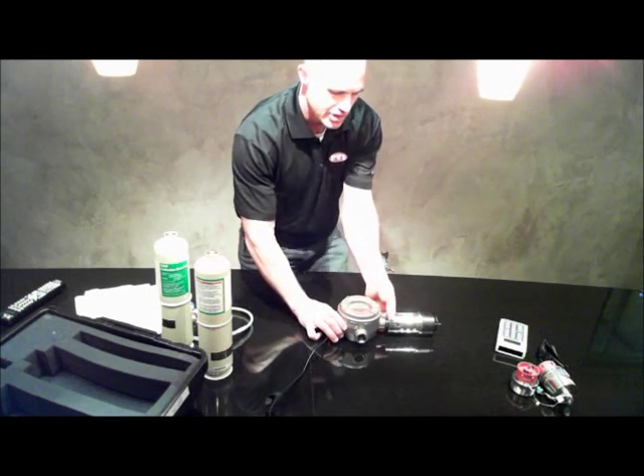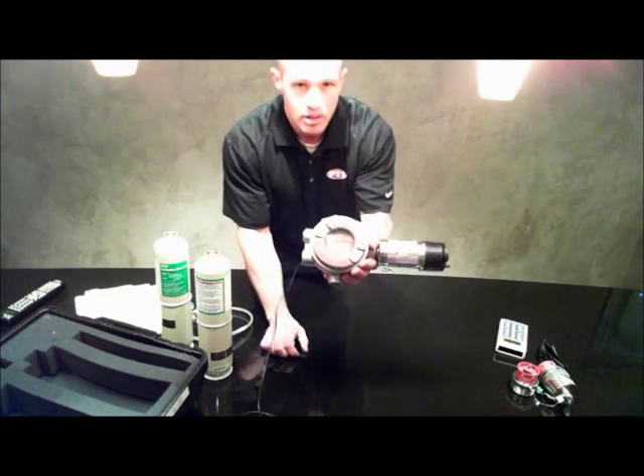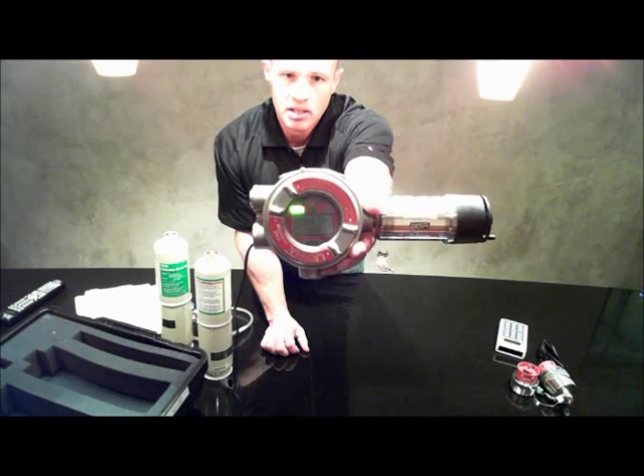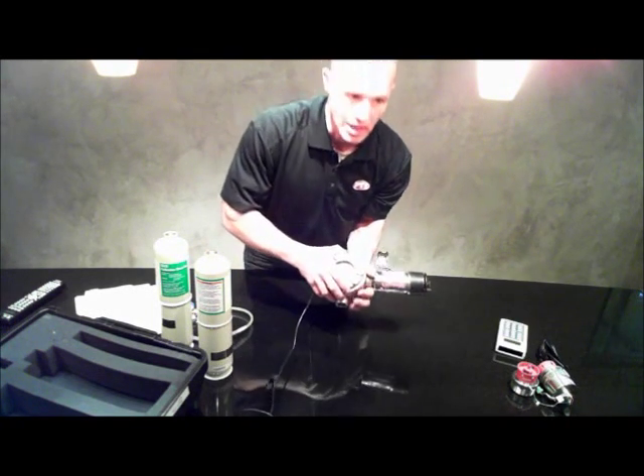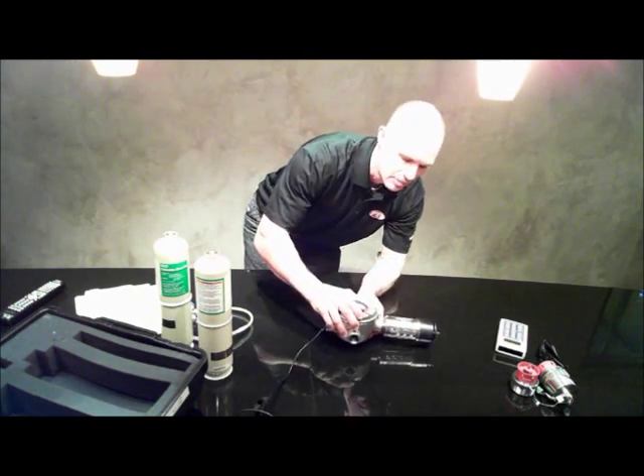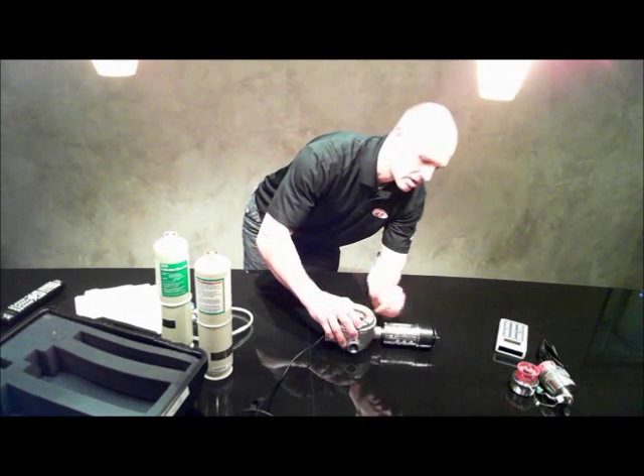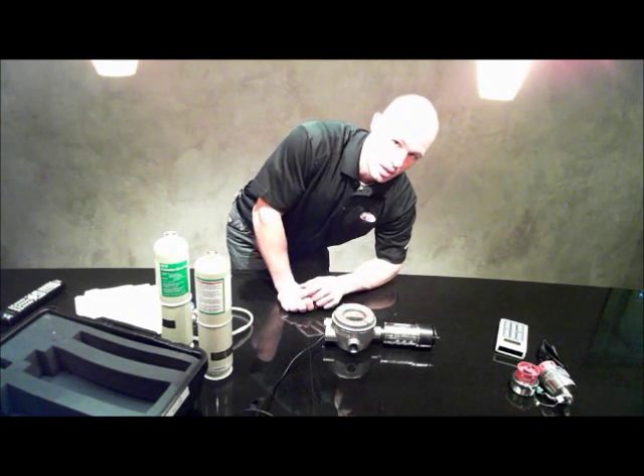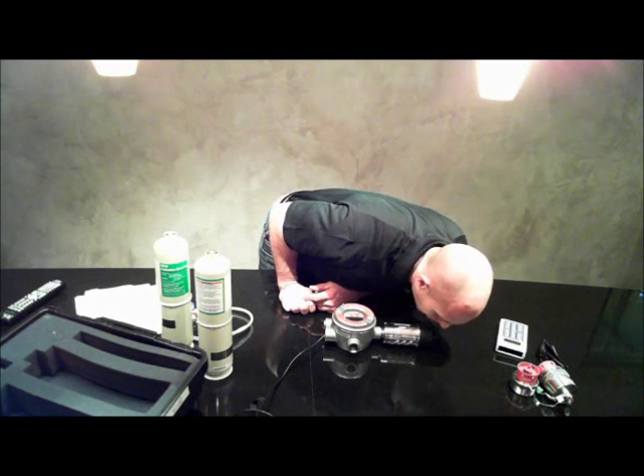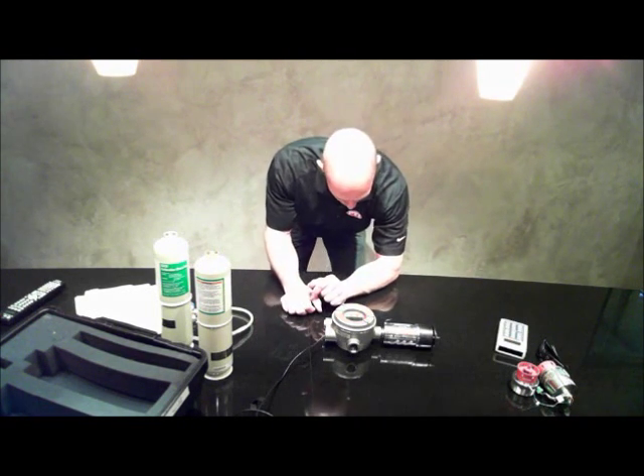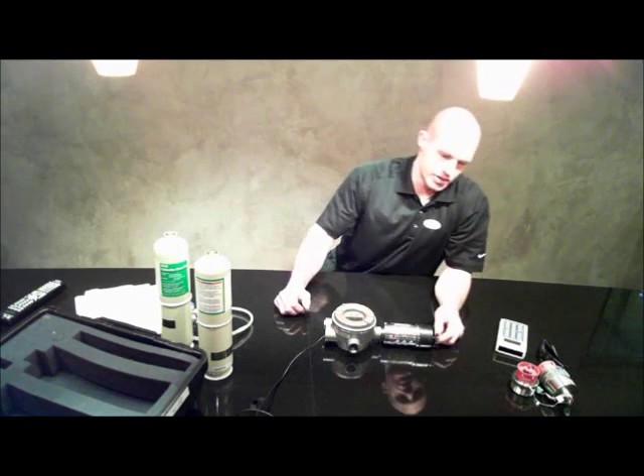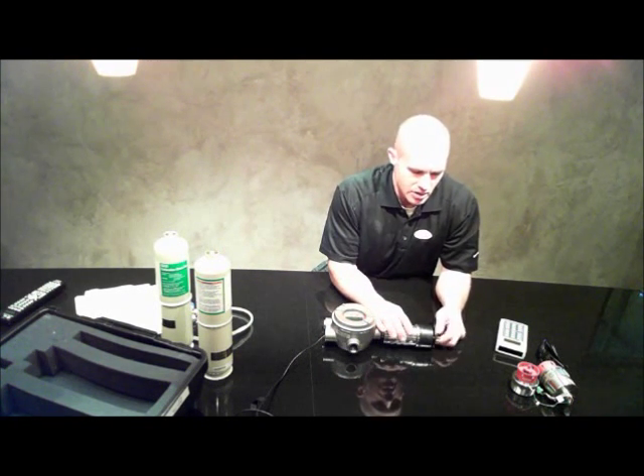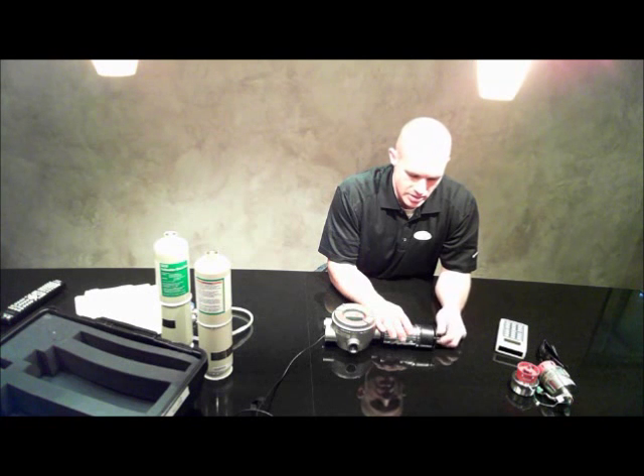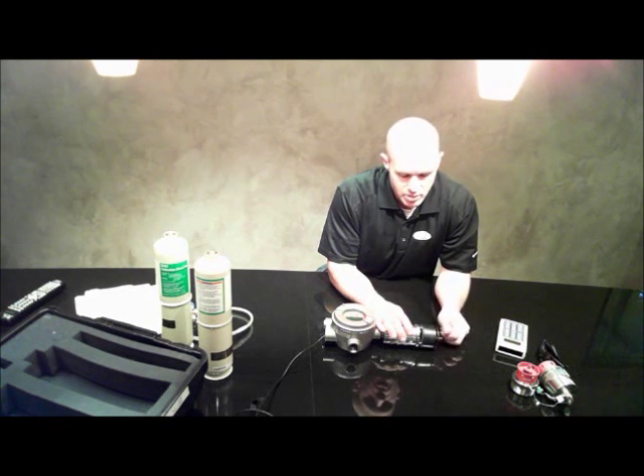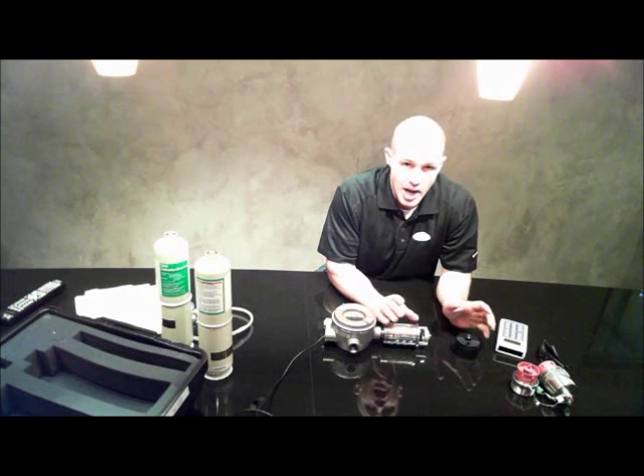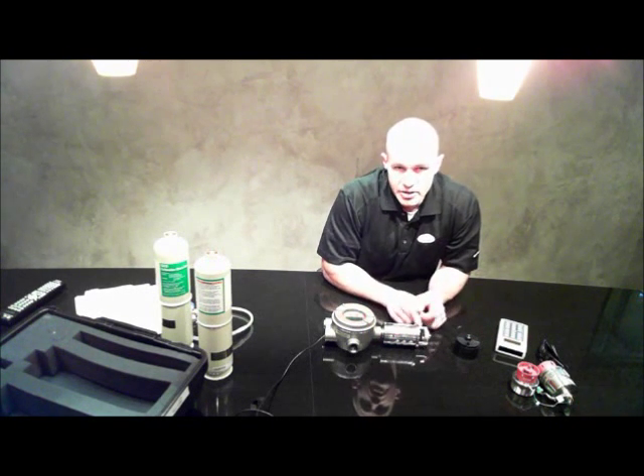It reads 50% LEL. Let's drop it down now. We've got the green light. Percentage reading. Again, there's about 2 minutes after a calibration that there can be gas present in this cap and it not set the alarm off. If you've got infrared style heads, one quick note is that it's a good idea to periodically check the lenses. If you get any kind of dust buildup or condensation or a dead spider or anything like that, it interferes with the signal in here.